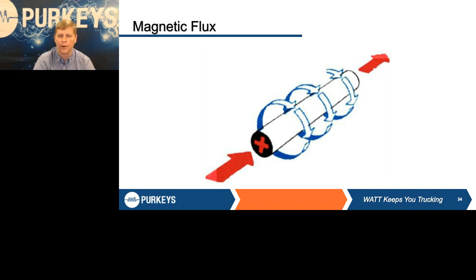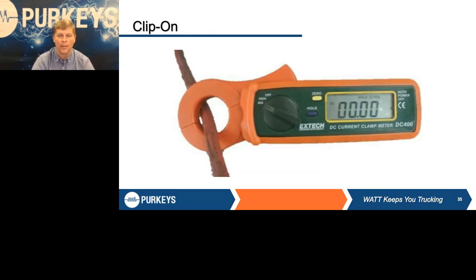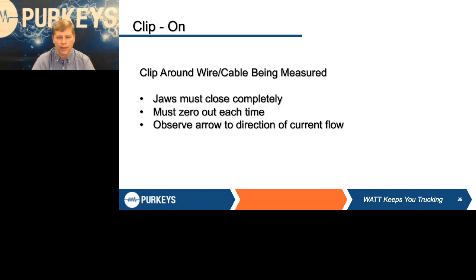A clip-on amp meter is going to register that magnetic field, or magnetic flux, and it converts it into a number. So it's based on, we see X amount of magnetic field being generated, you must have 37.5 amps going through this wire. Now, a couple things you got to be very careful about. Whenever you go to use this meter, if the jaws don't close all the way, it's not going to give you a fair reading.